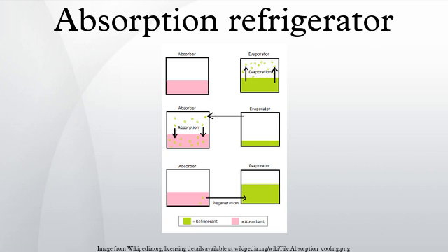Absorption: The now gaseous refrigerant is absorbed by another liquid, reducing its partial pressure in the evaporator and allowing more refrigerant to evaporate. Regeneration: The refrigerant saturated liquid is heated, causing the refrigerant to evaporate out. This happens at a significantly higher pressure. The refrigerant is then condensed through a heat exchanger to replenish the supply of liquid refrigerant in the evaporator.